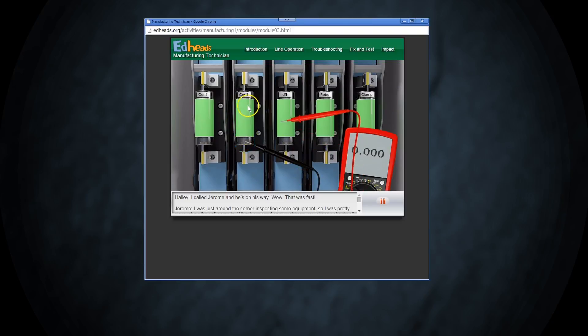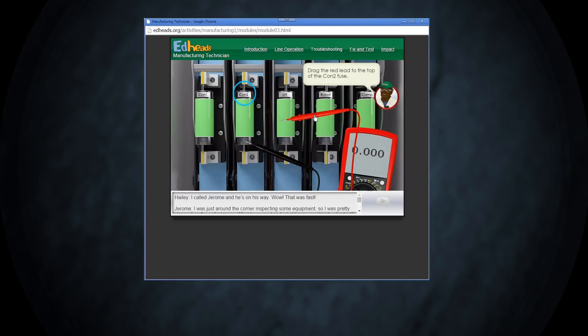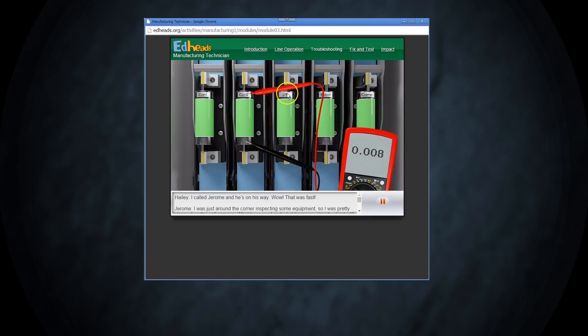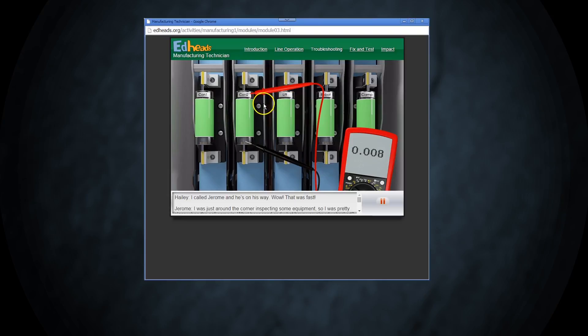Now take the red lead of the meter and hold it against the top of the conveyor belt fuse. Then read the meter and record on your worksheet what voltage you have showing. The meter should read close to zero if we have a good fuse. If it is bad, it would show close to 480 volts going in and nothing coming out.